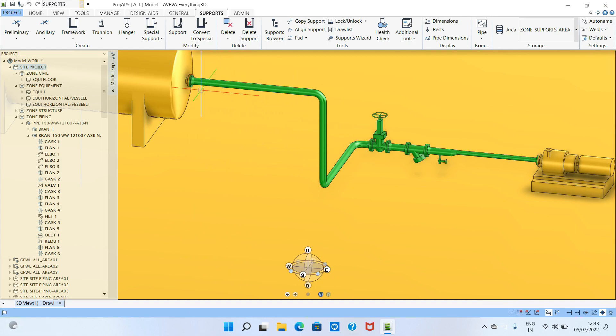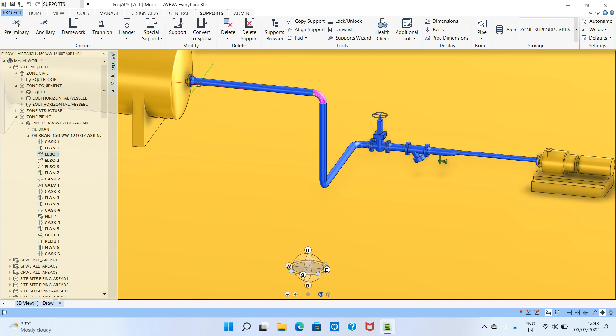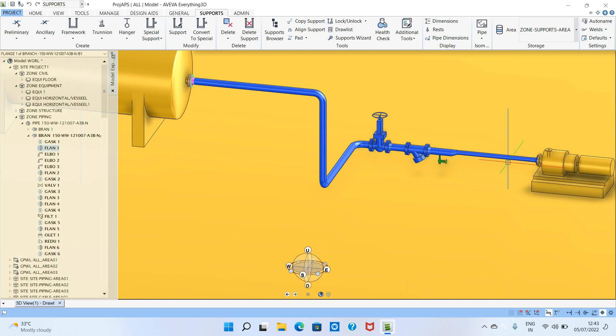When you start modeling supports, it is mandatory to know the flow direction of the piping. This is suction piping, so the flow comes from the nozzle to the pump. You need to start from the head — the starting point. This is very important. If you start from the reverse direction, it will reflect errors in the isometric, where the flow arrow and support tagging will be in reverse order.